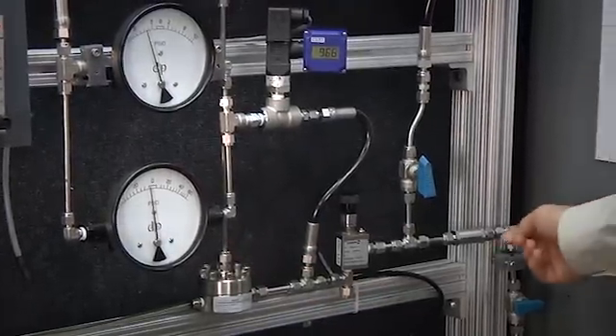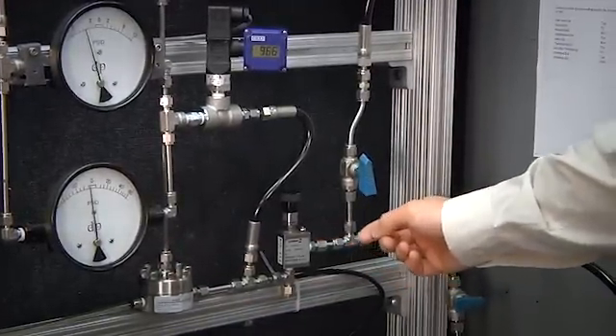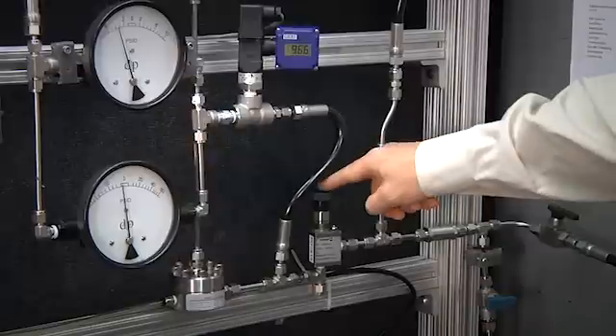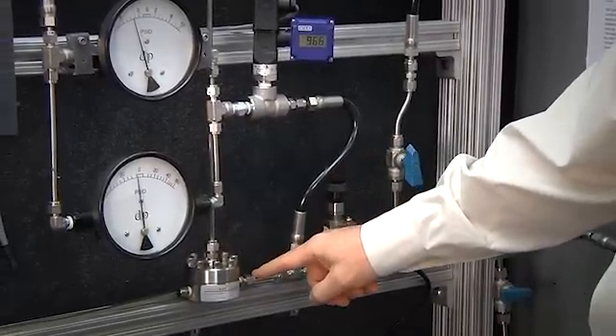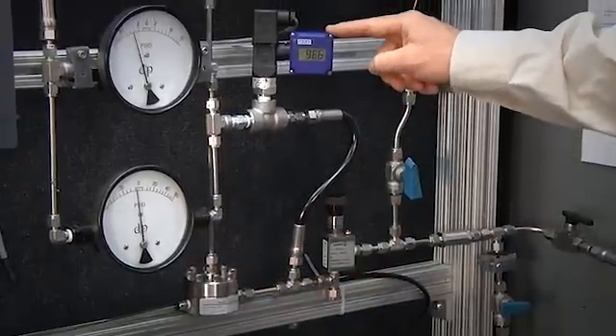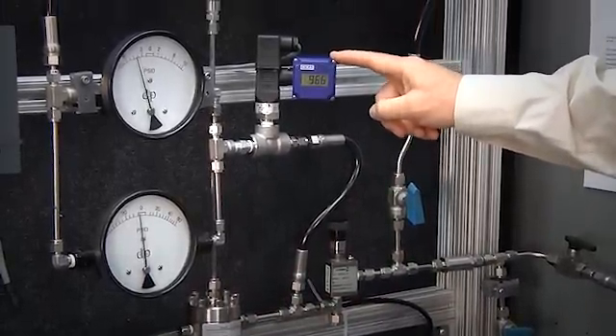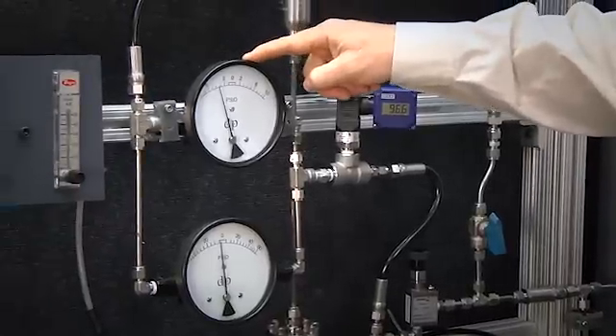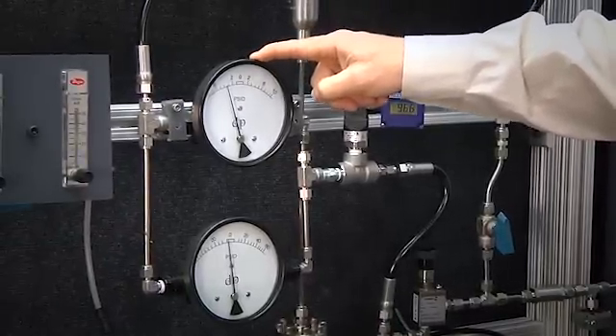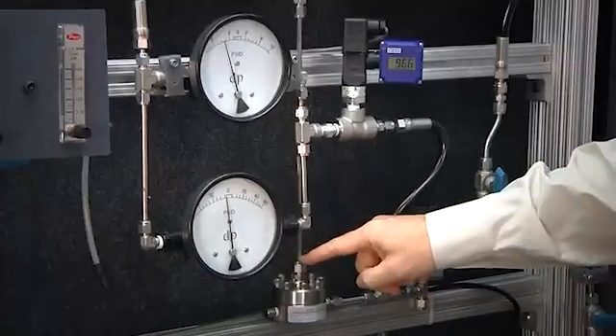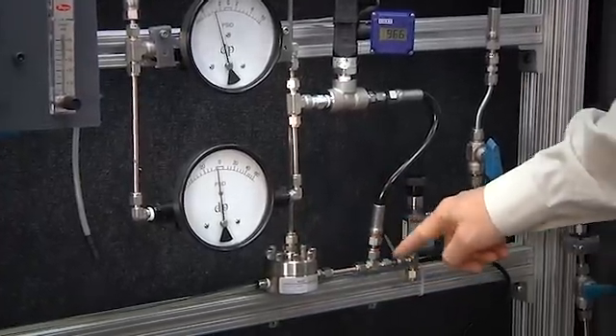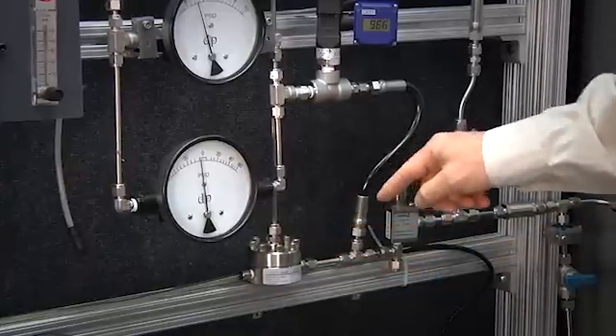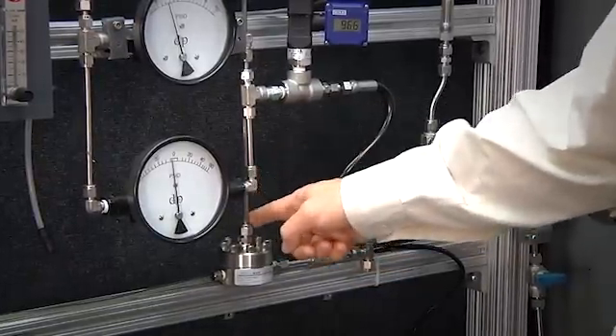We are going to bring in nitrogen gas on the inlet of the regulator through this micro needle valve. We are going to monitor the inlet controlled pressure both with this pressure transmitter here and also with this differential pressure gauge. We are actually measuring the slight difference between the pilot set point that we are providing and the controlled inlet. Right now the inlet is about 4 psi higher than the set point.